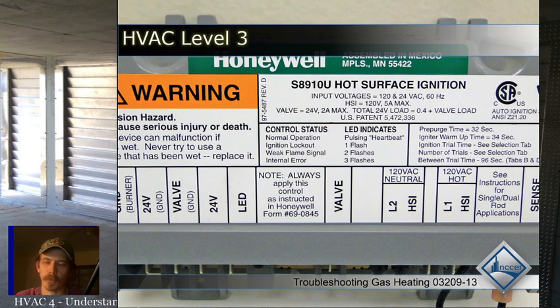But like we said before, it could be the opposite. So that's the first thing you want to do, is verify proper voltage to it. If you're calling for heating, or no, let's talk about cooling. If you're talking about cooling and the reversing valve should be on, then you check for 24 volts at the coil.